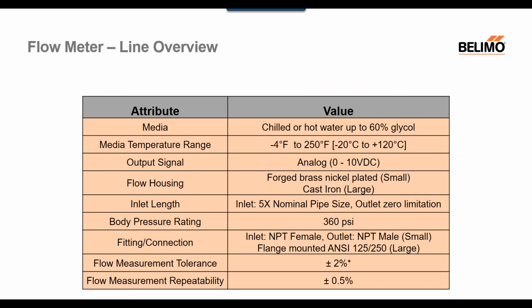Belimo's flow sensors can be used in chilled or hot water and in media with up to 60% glycol content and covering temperature ranges from -4 to 250 Fahrenheit or -20 Celsius to 120 Celsius. The flow sensors provide a linear output of 0 to 10 volts, providing compatibility to all BMS controls. The housing is manufactured out of forged brass housing for sizes 1/2 inch to 2 inch, and for the larger sizes 2.5 to 6 inch are cast iron flanged versions. Accuracy is plus or minus 2%, and the flow measurement repeatability is 0.5%.